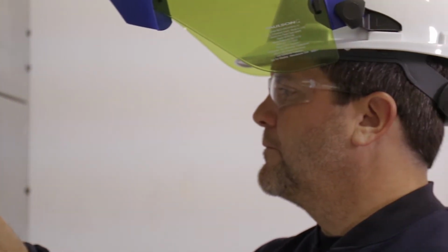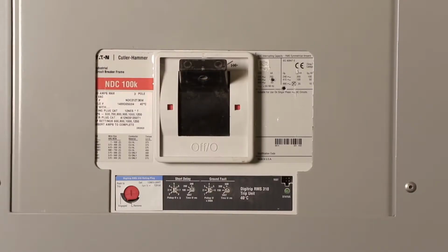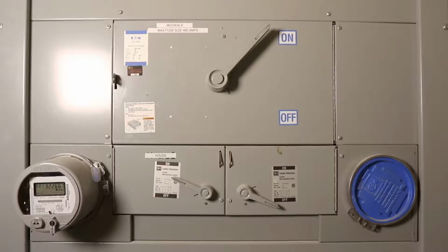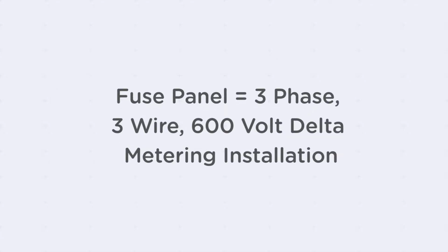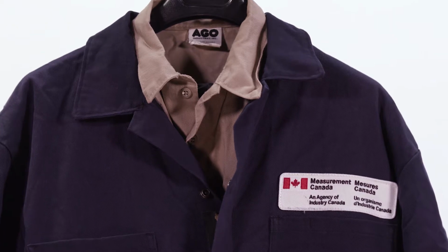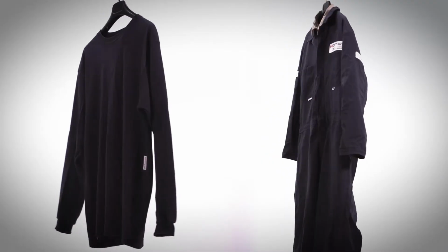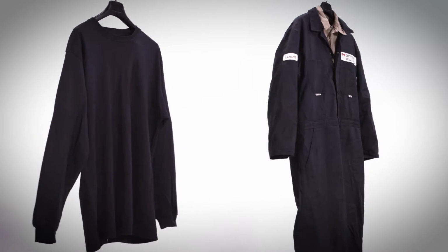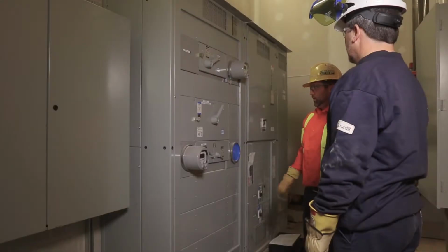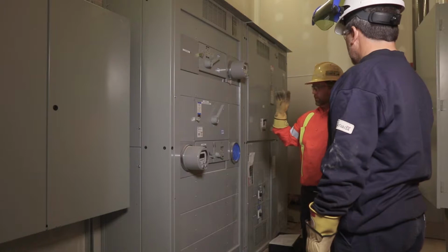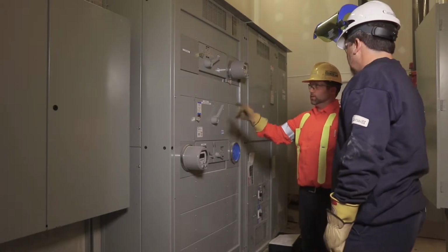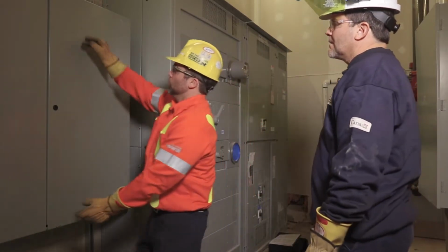Category 3 arc flash PPE is recommended if an employee is taking voltage readings in a fuse panel of a 3-phase 3-wire 600-volt delta metering installation. Follow all posted incident energy labels and consult with on-site personnel to determine if Category 2 PPE is permitted. A minimum of Category 2 arc flash clothing is required for a typical multiple customer metering system or MCMS installation. Follow all posted incident energy labels and consult with on-site personnel to determine if Category 3 PPE is required.